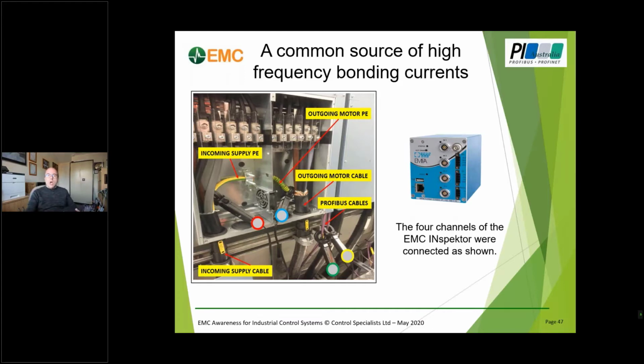This particular drive was chosen not because it was problematic, but simply because it was near me and it was a big one. We got the electricians to take the cover off, and I connected 4 probes, the clamps, as follows: two of them around each shield of each PROFIBUS cable, one around the green and yellow — what we'd call the earth, the protective earth in the supply cable — and one over this twisted shield.